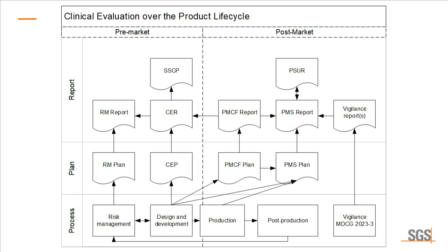You can see there's interaction between them, so they are not completely separate. In some cases, you want to copy some information from one to the other, or maybe you can just refer from one to the other. But overall, the conclusions to each of these reports are distinct, and so you will need to generate all of these different deliverables and maintain them as required by the MDR.